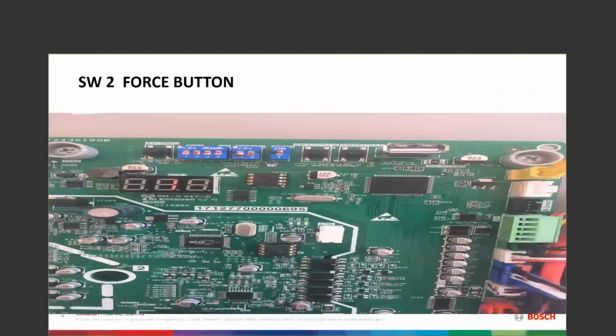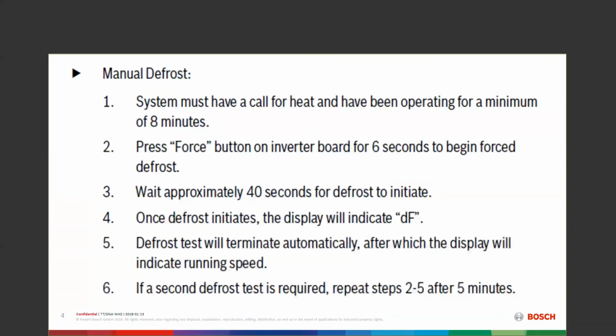The SW2 force button, we're going to push it now. We're going to make it go into defrost. There are several things that allow our system to go into defrost. It's going to take about 35 seconds probably for you to see that DF on your display. Your outside fan will stop, your reversing valve will de-energize and will be in the air conditioning mode. It will complete its defrost scenario even though you pushed it. You don't have to push it again to get it out of defrost. It'll come back out of defrost when it's ready to.